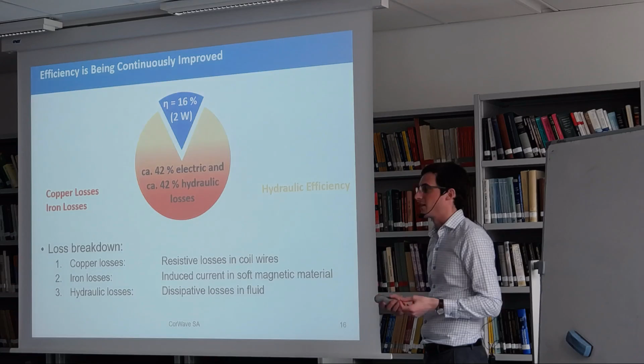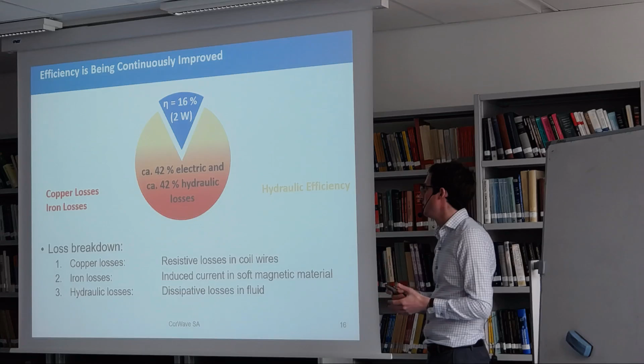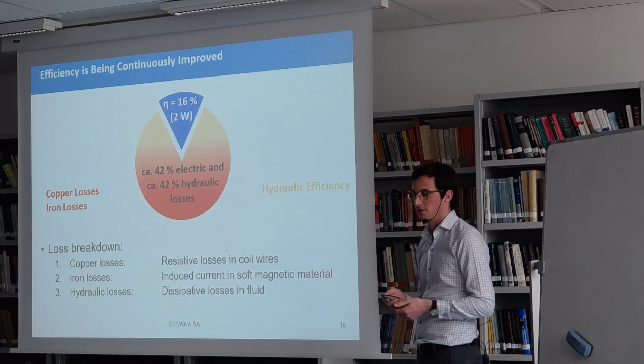Then we have so-called iron losses through the magnetic field which is generated - some of the magnetic field is dissipated in the iron material that makes up the actuator. Those are the losses in the actuator. Then we have the hydraulic losses, the dissipative losses in the fluid, which are much more difficult to optimize because it's harder to pinpoint exactly where they occur.